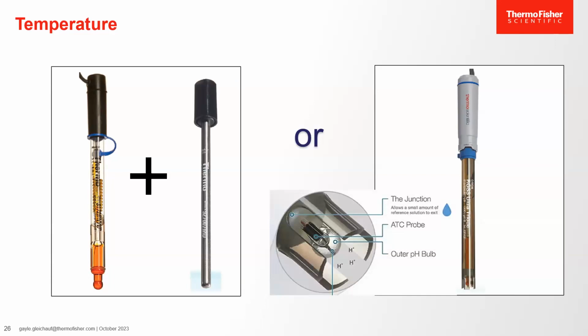So how do we decide? Well, an ATC will usually last for years. So when it's time to replace the pH electrode, we can keep the ATC and continue to use it. On the other hand, having a triode means we only need one probe to make the complete measurement of pH and temperature. A triode fits into a smaller container, so we need less volume than if we have two separate electrodes. Triodes come in a limited choice of pH electrode styles.